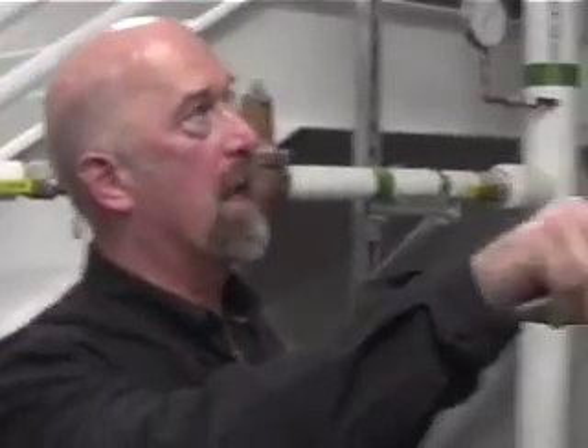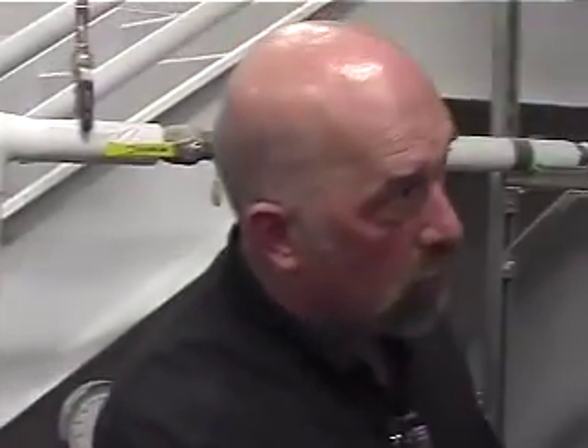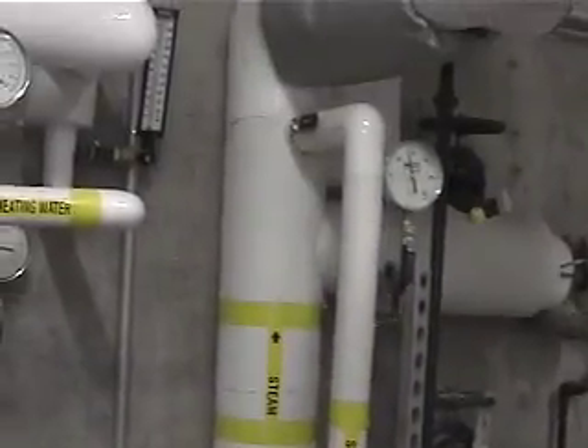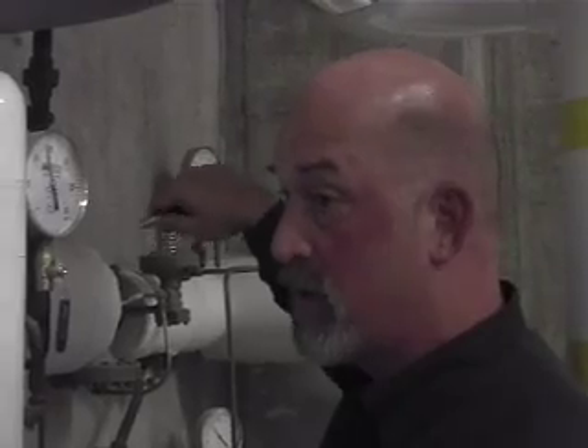And then this is the drip pan elbow that comes out of the vent right here. We've got like three-quarter inch there, going back in, going down here into your blowdown. Is that the line size off of the drip pan? That's the size right here, coming off the drip pan. That's just to drain the drip. Say for some reason it overpressurizes the system and the relief valve pops off, there's going to be flash steam in this vent line, so when it condenses, we need to drain the water off.